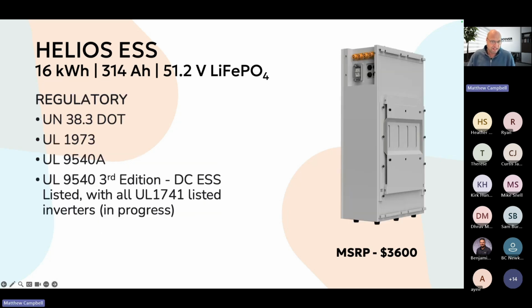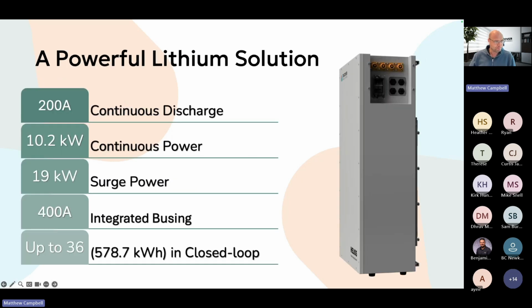As far as regulatory is concerned, all the regulatory you'd come to expect - 38.3 for shipping, the batteries all have 1973. They currently have the 9540A test complete, and we're in progress on the UL 9540 third edition DC ESS, which means you'll be able to pair this battery with all 1741 listed inverters. That's in progress, with an expectation to complete by summer. So for now, the battery will be available without UL 9540, but it's in the works and coming soon.